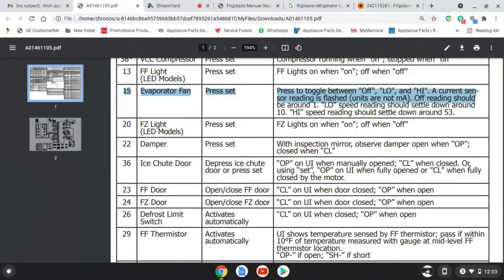It just increased. A good test you could do here is check your damper, make sure you're getting airflow on both sides. Check your return damper, make sure it's not obstructed. But I've got a good evaporator fan, so at that point that error wouldn't be valid. But let's say it's not spinning - it is in this case, but let's say that it's not.